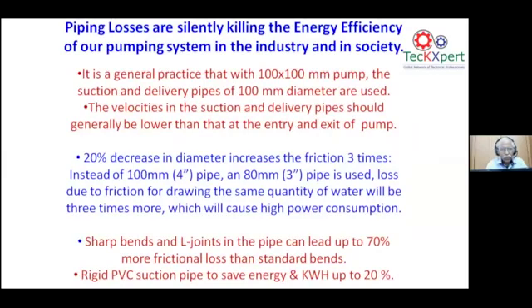You are having a 4-inch pipe, you are having a 4-inch pump, let us say the delivery and the suction, at least those fittings have to be changed at the time of the post-COVID crisis, at the post-COVID startup operations. These are all the areas where the choke is more in the system that has to be removed, because after all the velocities at the suction and delivery should generally be lower than the entry and the exit. That has to be maintained.